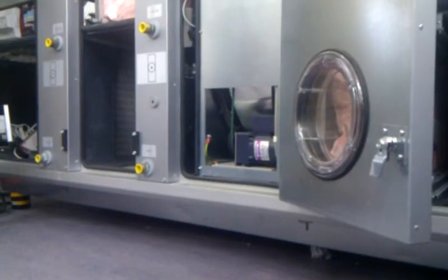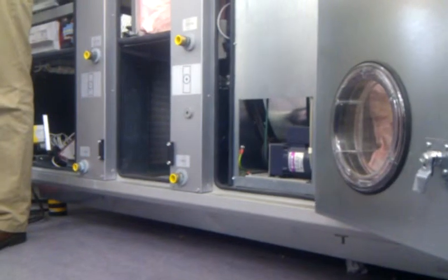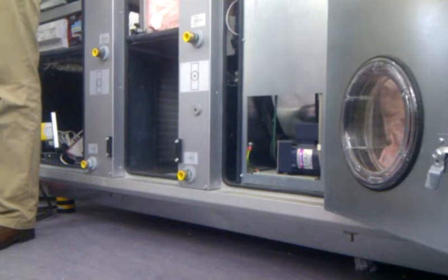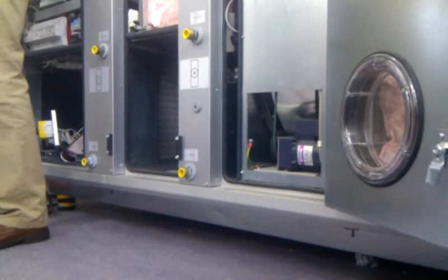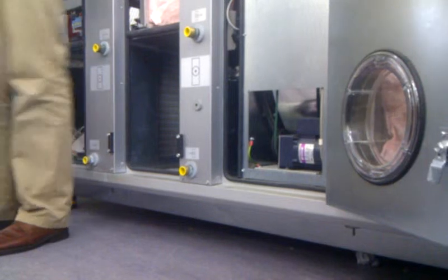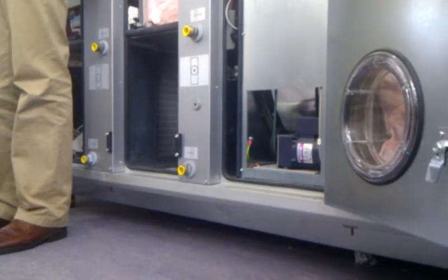And here's our fan for our supply. That blows the air out this one and up and out through whatever we want to supply into our room. And then on the return, we just suck the return back in here. It can be sucked from a duct anywhere. But return is not crucial because you can suck return nearly from anywhere in a big room. Because once you get the fresh air and the conditioned air out where you want it, you can suck it back up one corner, no problem. So that's most industrial applications. Other than clean rooms, you're not really that worried about where you suck back the air from.